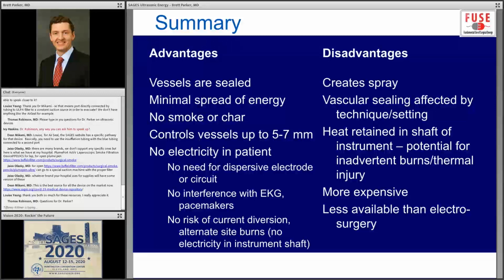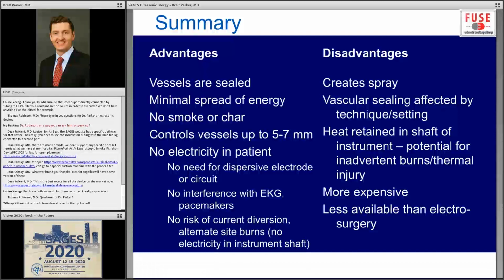So the answer before, it's interesting, it's a bit paradoxical in the sense that the ultrasonic device has a higher temperature and then results in residual heat injuries, as Dr. Parker said. And so it's a little bit counterintuitive why the lateral spread is less with an ultrasonic device, and that's because if you look at lateral spread, it's a coefficient multiplied by a delta in the temperature, and the coefficient has to do with the thermal mass of the tip of the instrument. The thermal mass of the tip of an advanced bipolar is much greater than that of an ultrasonic device, so even though the ultrasonic device gets much hotter, because the thermal mass is lower, the lateral thermal spread is less.